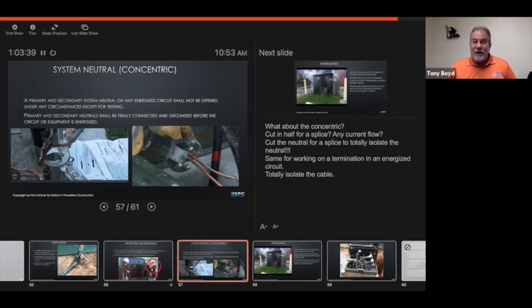And, do cars always hit poles? Well, in our line of business, it does happen more frequently than you suspect. Do trucks grab guy wires and get conductors together? They still do. We had one that was reported about 2 weeks ago, I believe. And the conductors got together, burned down, actually contacted the neutral, and energized the neutral with the current carrying conductor. Okay, so in our underground systems, is the concentric neutral a neutral current carrying conductor? The answer is yes, it is.